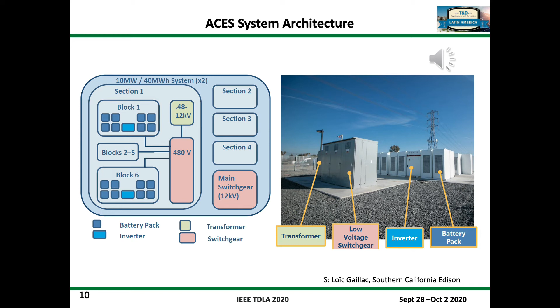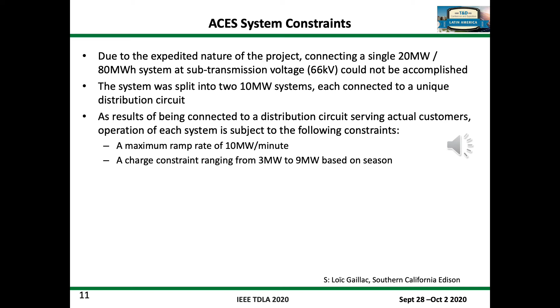There are a few constraints that this Aliso Canyon energy storage system encountered during implementation. The project had a very short timeline, so it was not possible to connect one single 20 megawatt, 80 megawatt-hour system at the subtransmission voltage of 66 kV. Therefore, the system had to be split into two systems, each connected to a 12 kV distribution circuit. As a result of being interconnected to a distribution circuit actually serving customers, the operation is subject to constraints: a maximum ramp-up rate of 10 megawatts per minute, and a charge constraint ranging from 3 megawatts to 9 megawatts based on the season.